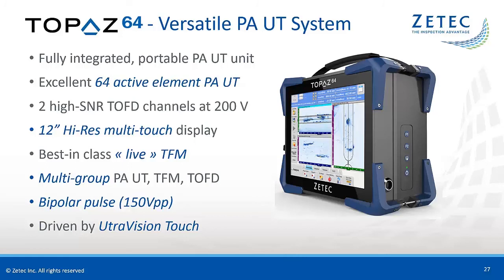The Topaz 64 allows to perform encoded scans, motorized or manually driven, and record live TFM frames or TOFD channels in parallel with one or more standard phase array channels. This allows to speed up the global inspection process. After the recording, the TFM is available as an actual merged data group in UltraVision Touch, and the TOFD data can be exploited like a standard phase array UT sector scan.